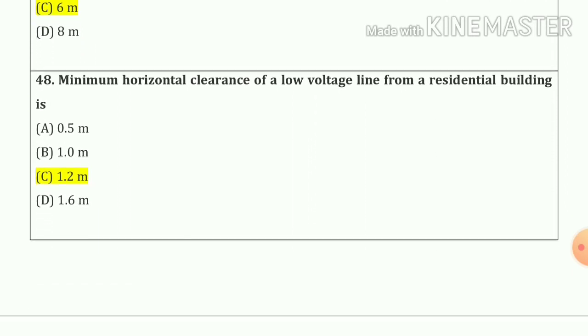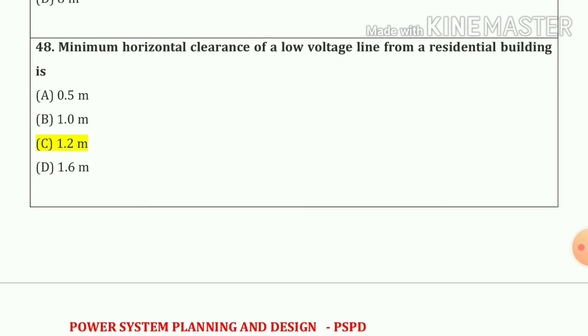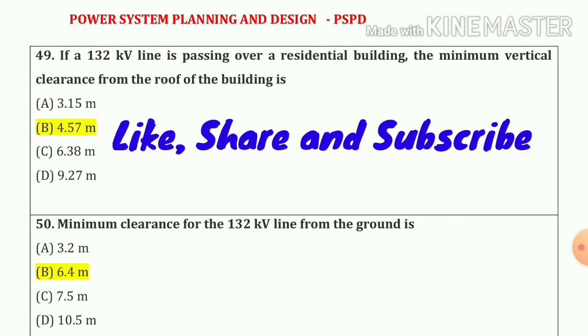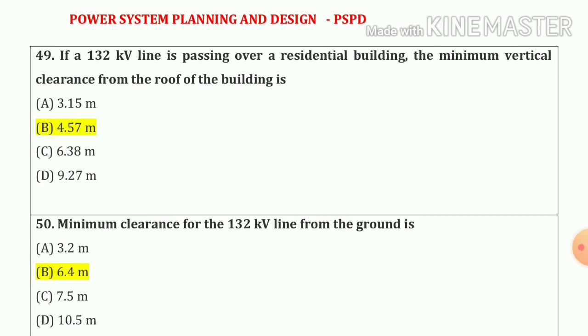Question number 48: minimum horizontal clearance of low voltage line from a residential building is 1.2 meters — option number C. Question number 49: if a 132 kV line is passing over a residential building, the minimum vertical clearance from the roof of the building is 4.57 meters — option number B.